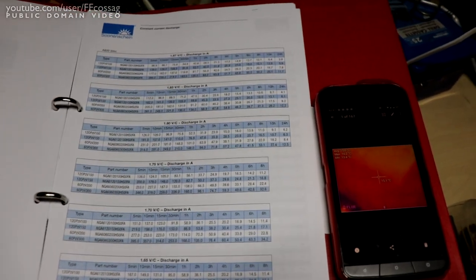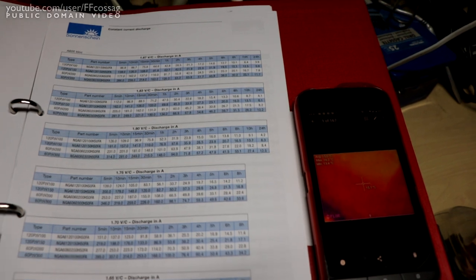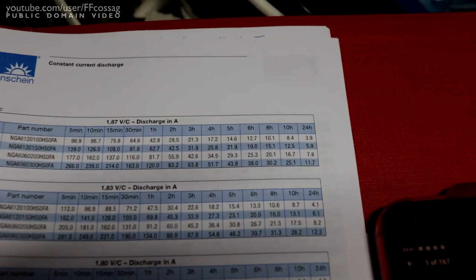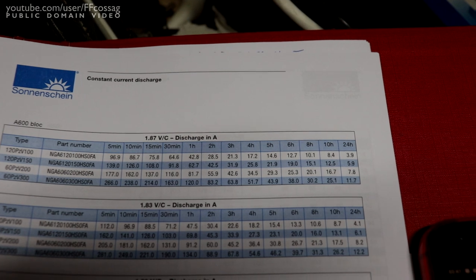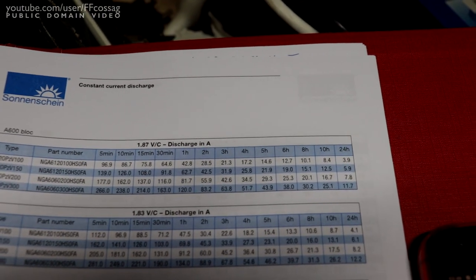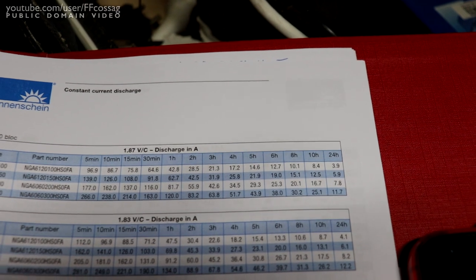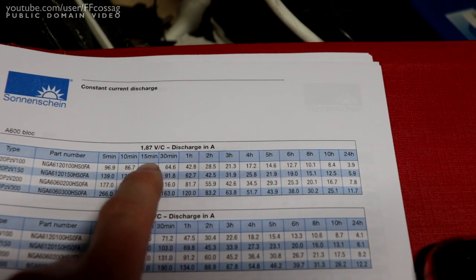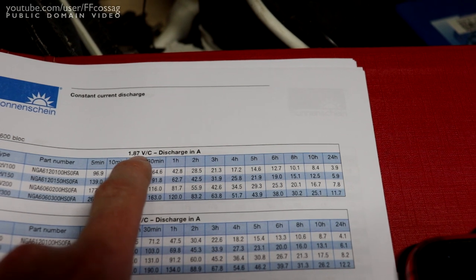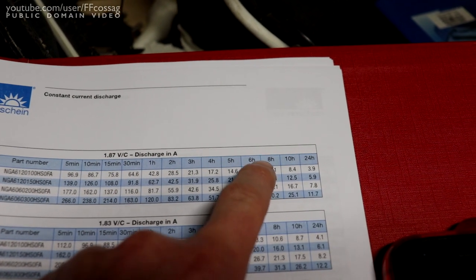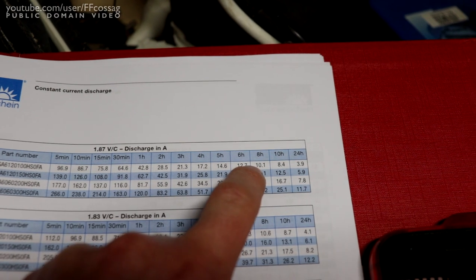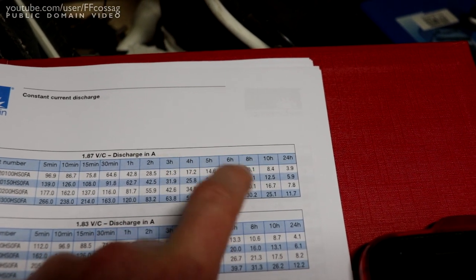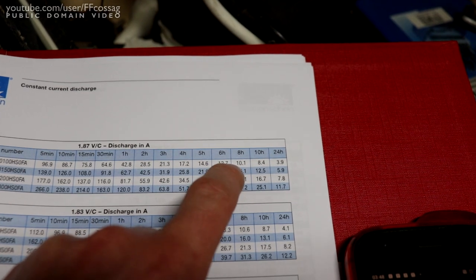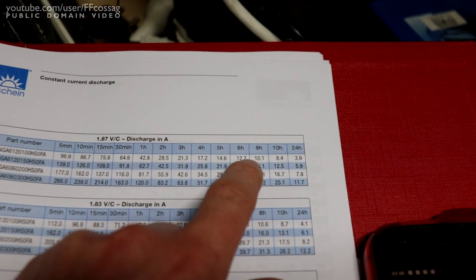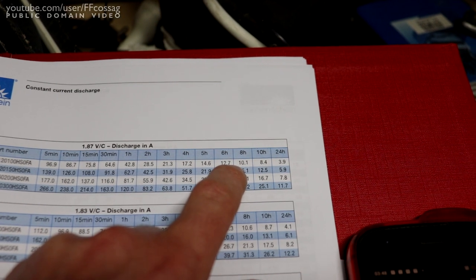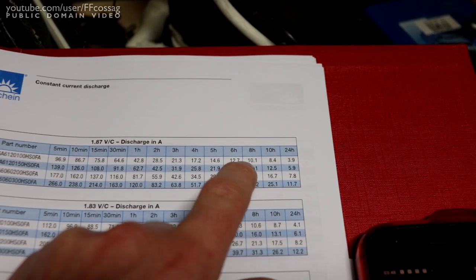Now, here we have the almighty data sheet at hand, and we need to remember we're doing a rather shallow discharge. So while it's tempting to think of these batteries as 100 amp hour batteries, we are not actually testing for 100 amp hours. We're doing a 1.87 volts per cell discharge at 10 amps for an 8-hour runtime, but 10.1 times 8, that's not 100 amp hours, that's 80.8 amp hours. So our 100 amp hour batteries are actually 80.8 amp hours when they're new at 20 degrees Celsius.